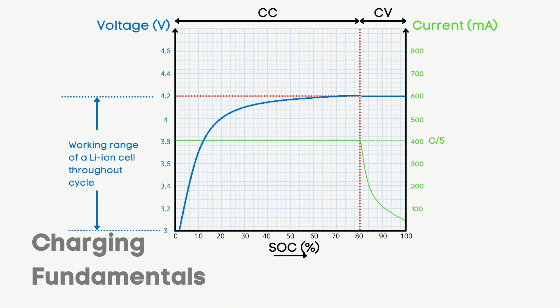Hence, a hybrid process of CC and CV is used, where a constant current is supplied to the battery until it reaches about 80% of SOC and near the peak voltage of the battery. After this stage, to keep voltage constant, the current supplied is gradually decreased. This means if we have to charge the battery optimally, we will have to keep the charging input to the battery variable.